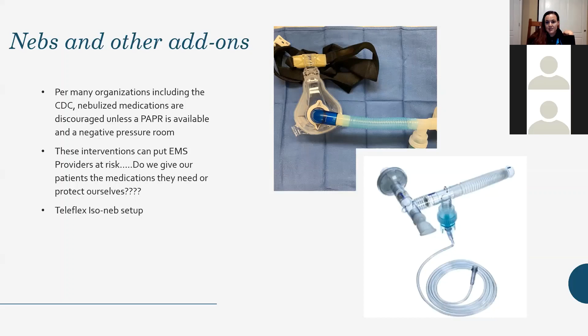Follow-up question from Travis: on the handheld, isn't there an opening for air to get out of the end of the rib tubing on the neb? Yeah, you just couldn't see it in that picture. That thing is supposed to push it back toward that bacterial filter. I think it's just to decrease the amount of pressure and flow in that corrugated tubing, because there's a full stop on the end of it, and it's supposed to direct all the expiratory flow out through the filter. So it's a pretty interesting device. I probably need to watch a little bit more on it, but like I said, I found this a couple hours ago when I was looking at ways to hook nebs into different devices and things like that.